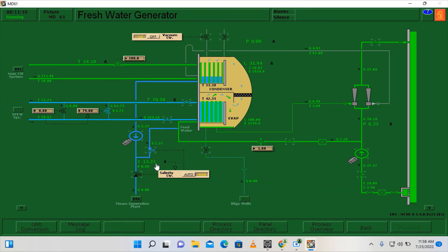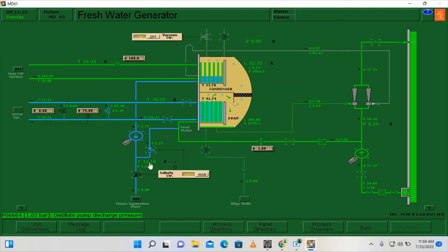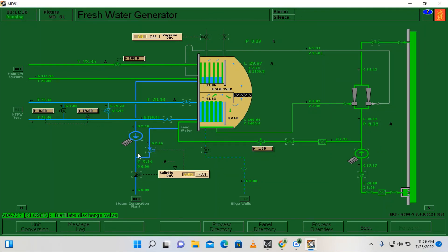Now it is already below 15 ppm. We can now put the salinity controller in automatic. When we switch the salinity controller to automatic, this means that once the salinity of our distillate water is already below 15 ppm, then it will be redirected to our distillate tank. If it is higher than 15 ppm, then this valve will close and this valve will open, which will dump the high ppm water mixed on our sea water line.